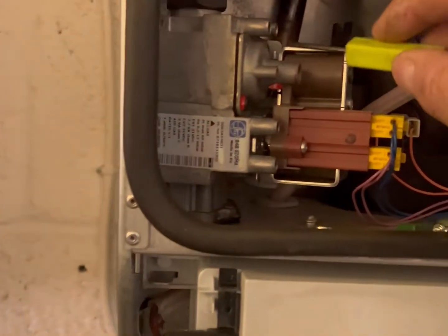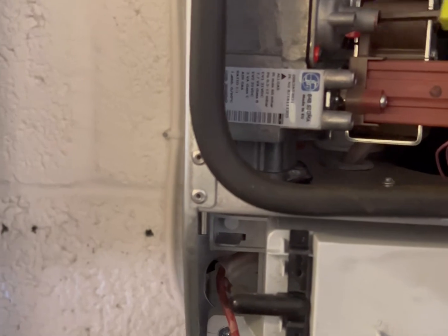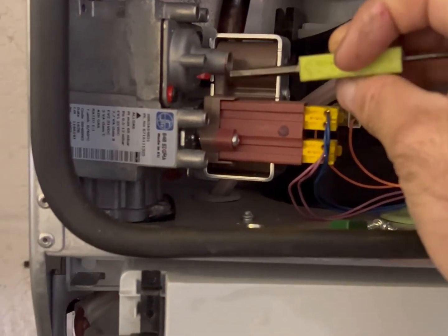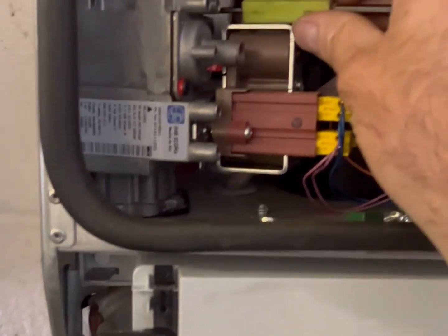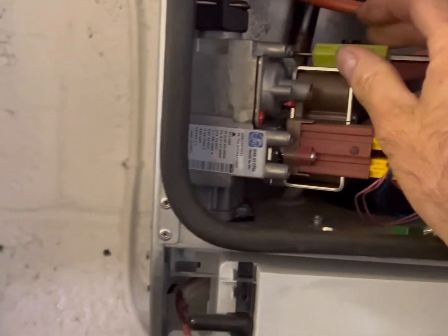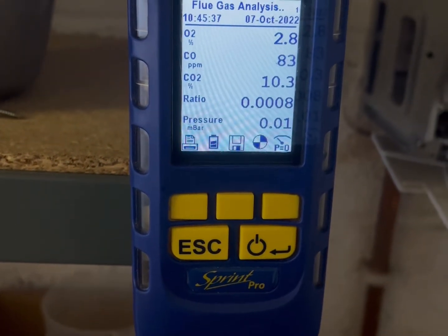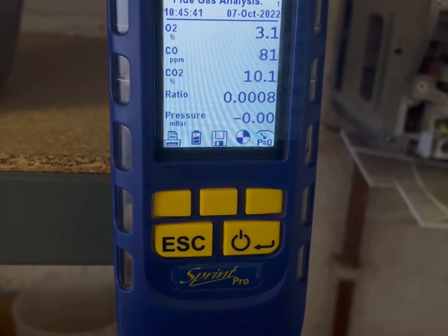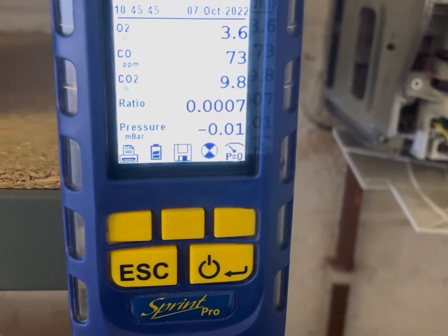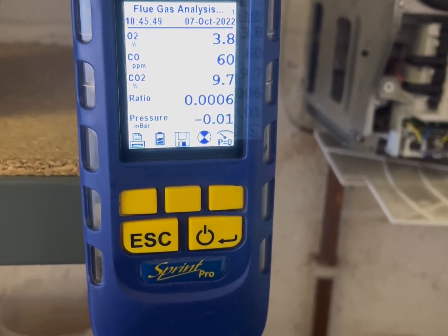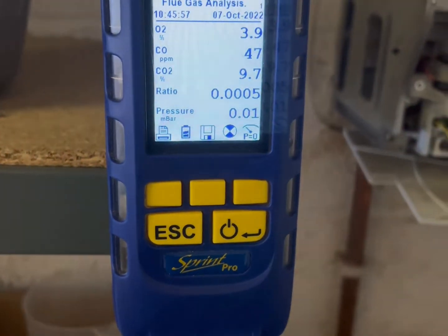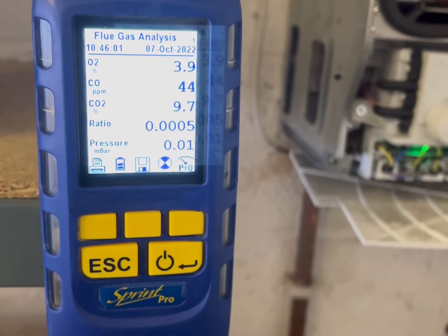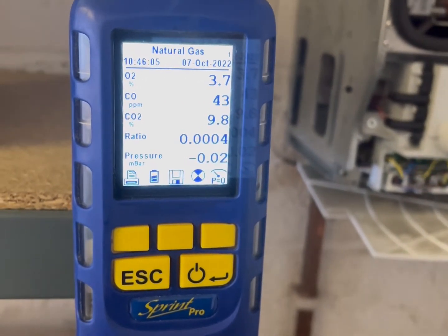The movement on the gas valve: we were coming down by going left, by twisting it towards me. On the maximum one, to go up you have to come towards me — it's the opposite. So on this one we want it to come down, so we want to come to the right. There we go — you can see it coming down now; it's only a small movement. We can come back up a tiny bit. There we go, so we're bang on.